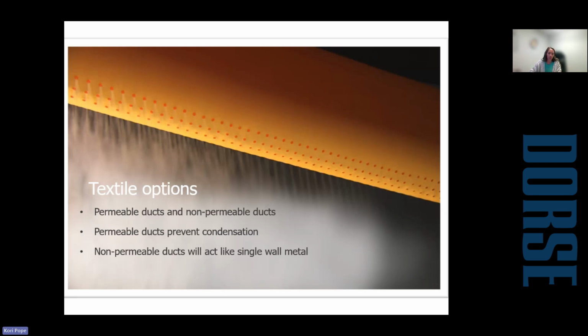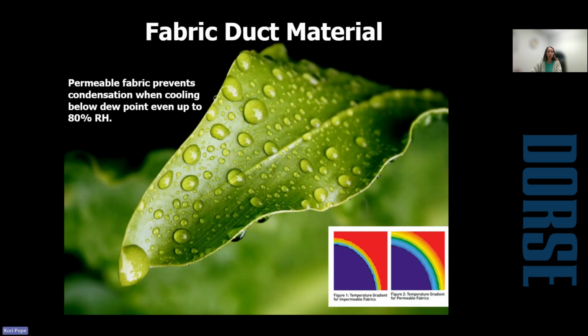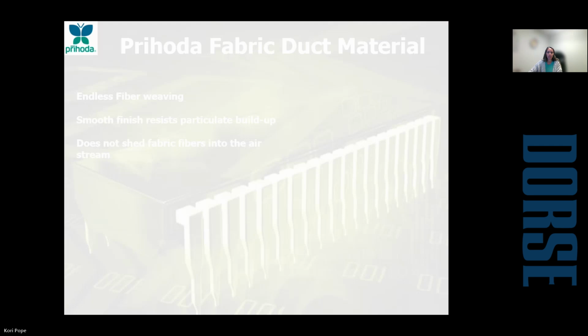However, we do offer a non-permeable option, and this will act more like a single wall metal diffuser. So if you have the right conditions with humidity and whatnot, you will run the risk of condensation with those. However, non-permeable duct does have its applications where it is most vital in. So like transfer only, if you're trying to get air from one room to another, non-permeable would be a great option, as well as heat only in those low humidity areas would be a phenomenal reason to use non-permeable. So all of our permeable ducts will prevent condensation when cooling below dew point, even up to 80% relative humidity.